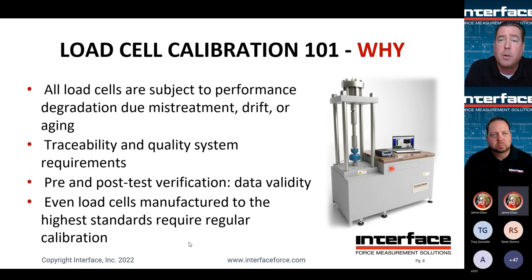Why do we calibrate? All load cells are subject to some sort of performance degradation due to mistreatment, drift, or aging. You're going to see some change in sensitivity over time. Perhaps the load cell is being used in a very abusive environment. Perhaps it's within the first couple of years of manufacture, and you're going to see some drift happen as a function of epoxies and different materials in the load cell aging. So no matter what, you're going to see some change in output from the load cell.